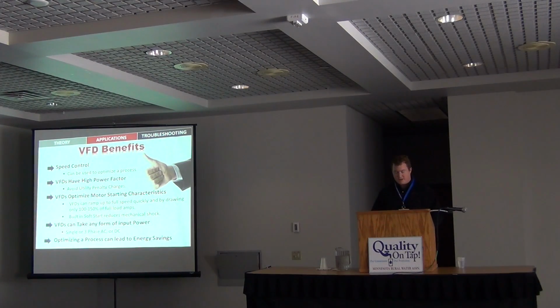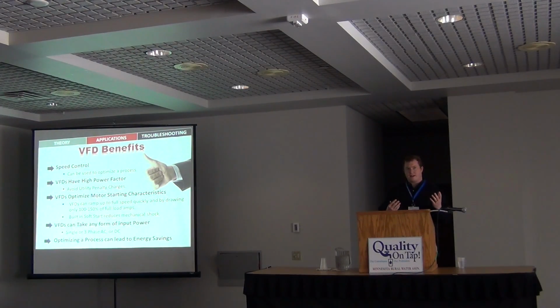VFDs have high power factor. Because we're doing this AC to DC back to a modulated AC conversion, we have almost unity power factor. A motor has a power factor of 0.7, 0.8, 0.85, somewhere in there. What that basically means is it has a certain ratio of real power to reactive power, or reactive power is also known as imaginary power. And the utility company doesn't like to supply imaginary power because they still have to generate it even though it doesn't really do anything. So VFDs have an advantage from that perspective.